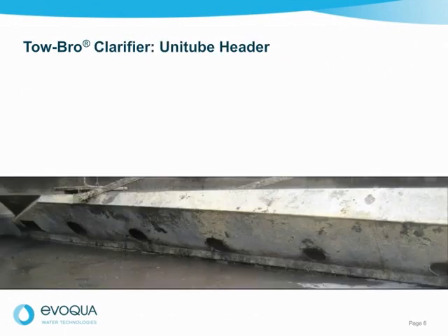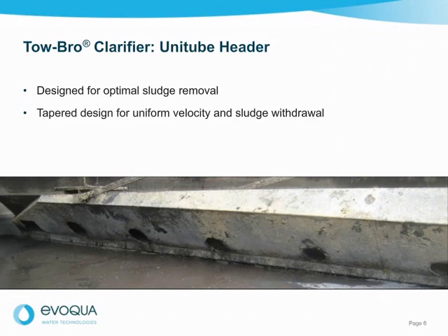Now let's talk about how this innovative technology works. The Tow-Bro system features a unitube header designed specifically for optimal sludge removal. The header features a tapered design, with the cross-section decreasing from the center of the tank — where the total sludge volume is maximum — to the outer tip, where the total volume is least, for a uniform sludge withdrawal velocity. The constant velocities prevent sludge buildup in the header and clogging.